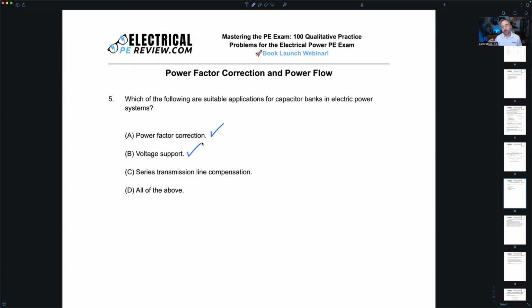And what that is, when the capacitor is supplying reactive current while it supplies reactive power, that reactive current cancels out a little bit of the inductive current drawn by the inductive loads. And what that does is actually decrease the current a little bit. Think about it. Lagging current lags the voltage, leading current leads the voltage. So the two of them cancel out. It's like having a positive number summed up with a negative number. So when the capacitive current cancels out some of the lagging current, your overall current decreases, which also decreases some of your voltage drop as the current flows through the conductor. As we decrease the voltage drop, what happens? Well, decreasing the voltage drop means I'm actually increasing the voltage available at the load, right at the load. That's voltage support, another application for capacitor banks.